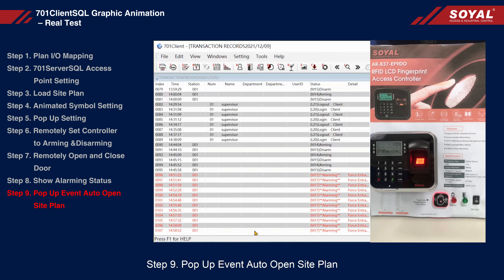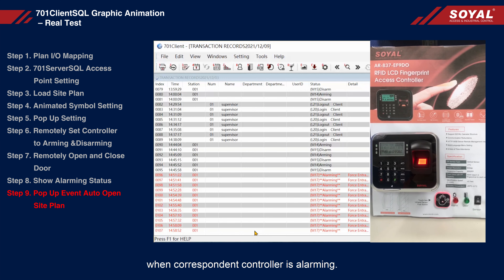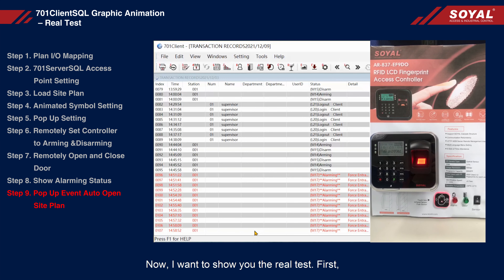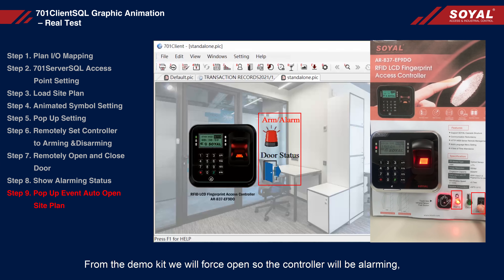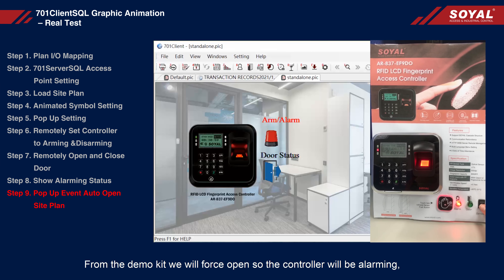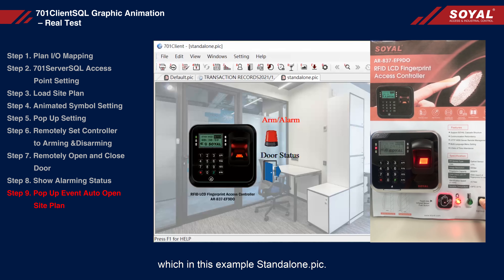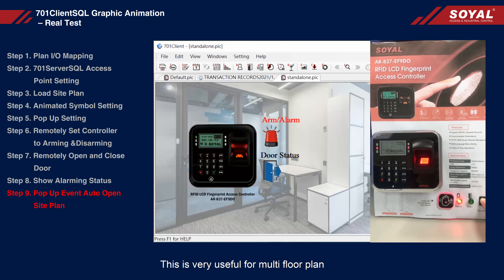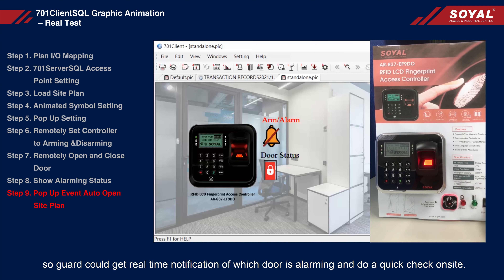Step 9: Pop-up event auto-open site plan. Back in Step 5's pop-up setting, we set the auto-open site plan 'standalone PIC' when the corresponding controller is alarming. Now I want to show you the real test. First, close the site plan and only keep the transaction window open. From the demo kit, we will force open so the controller will be alarming. As you can see, 701 client SQL will automatically open the corresponding site plan — in this example, standalone PIC. This is very useful for multi-floor plans so the guard can get a real-time notification of which door is alarming and do a quick check on site.